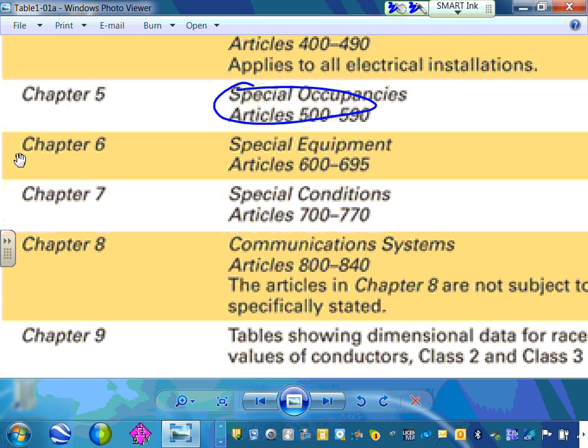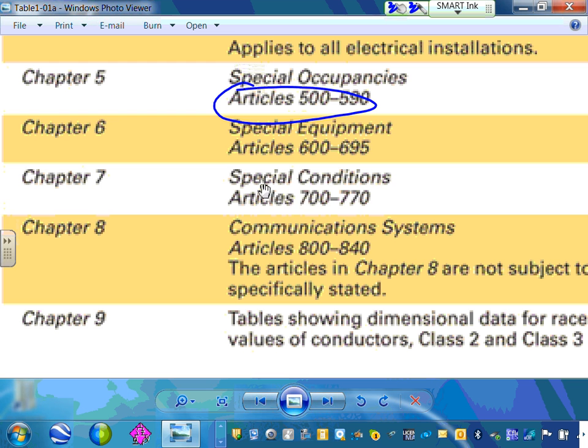Special equipment is in Chapter 6, and special conditions in Chapter 7—typically fire alarm, security, phone, data. Fire alarm and security are typically covered there. We'll talk about these in the spring when we cover emergency systems, legally required standby systems, and other systems required in the building under Chapter 7.